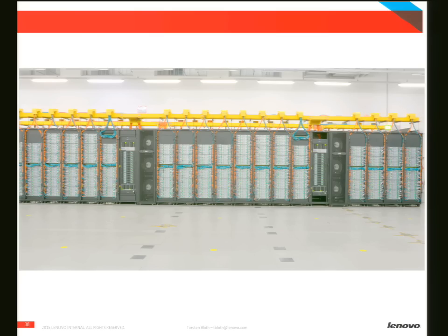They are using free air cooling. What they simply do is they pump the hot water to the roof of the data center, and they let it cool by the outside air. So the temperature of the system itself varies according to summer or winter times. In winter, the normally operated water temperature is much lower because it's just colder outside. And in summer, we get up to 45 degrees inlet temperature because it's simply hotter outside.